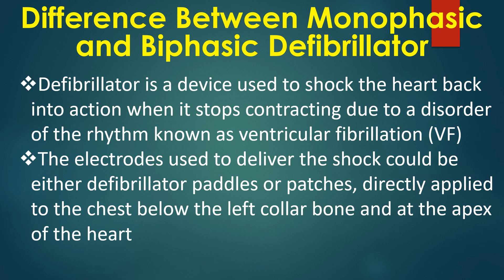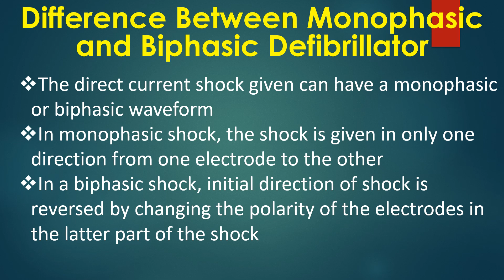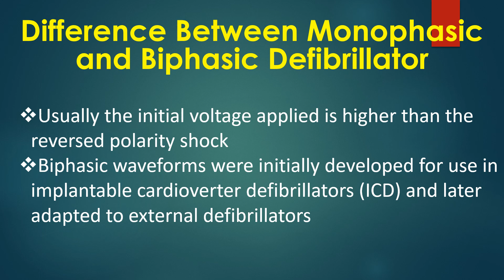The direct current shock given can have a monophasic or biphasic waveform. In monophasic shock, the shock is given in only one direction from one electrode to the other. In a biphasic shock, initial direction of shock is reversed by changing the polarity of the electrodes in the latter part of the shock. Usually, the initial voltage applied is higher than the reverse polarity shock. Biphasic waveforms were initially developed for use in implantable cardioverter defibrillators and later adapted to external defibrillators. Biphasic truncated exponential waveform and rectilinear biphasic waveform are two types of biphasic waveforms used by different manufacturers.